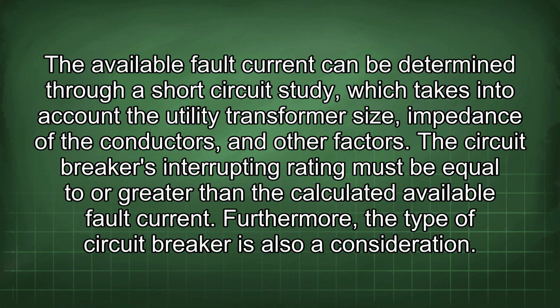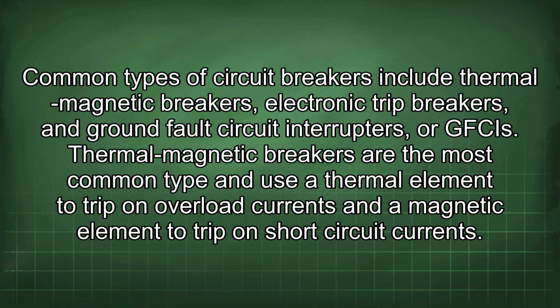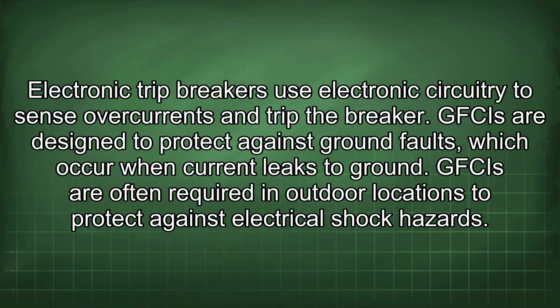Furthermore, the type of circuit breaker is also a consideration. Common types of circuit breakers include thermal magnetic breakers, electronic trip breakers, and ground fault circuit interrupters, or GFCIs. Thermal magnetic breakers are the most common type and use a thermal element to trip on overload currents and a magnetic element to trip on short circuit currents. Electronic trip breakers use electronic circuitry to sense overcurrents and trip the breaker. GFCIs are designed to protect against ground faults, which occur when current leaks to ground. GFCIs are often required in outdoor locations to protect against electrical shock hazards.